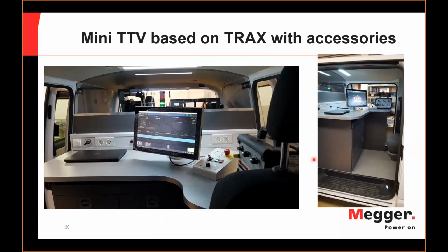Recently, we also made a mini solution. So a solution that only has one instrument on board. It means that it's a cheaper version, and it lacks all the switch boxes that we have on HV side and on LV side. But since the instrument is so multifaceted, multifunctional, it still can cover, let's say, 60% of all the tests that are needed to assess the condition of the transformer.